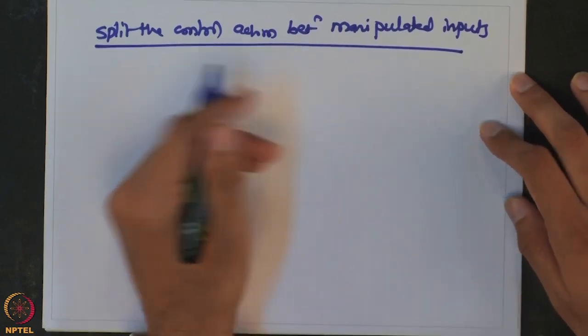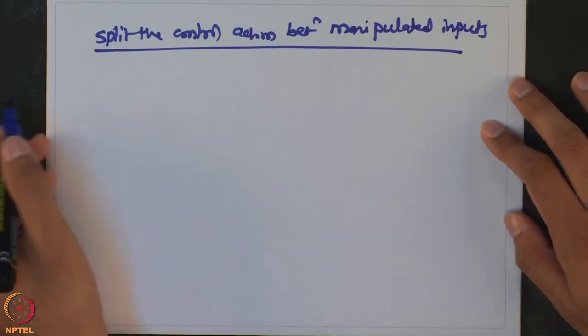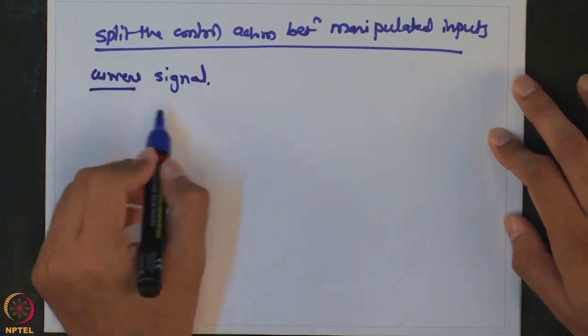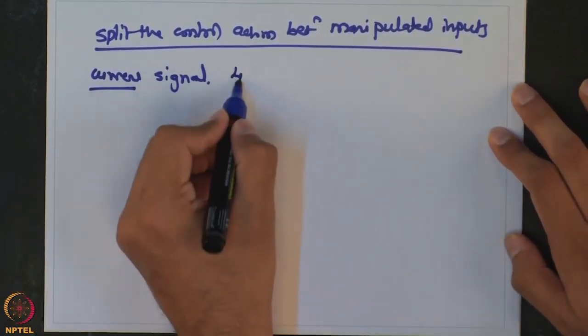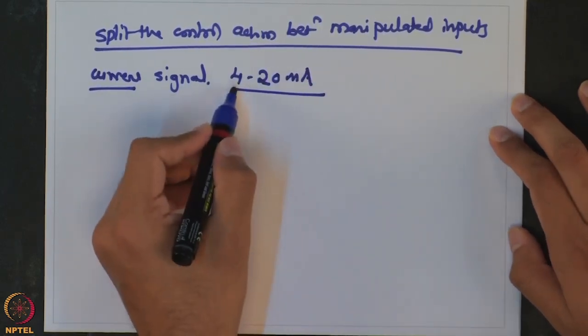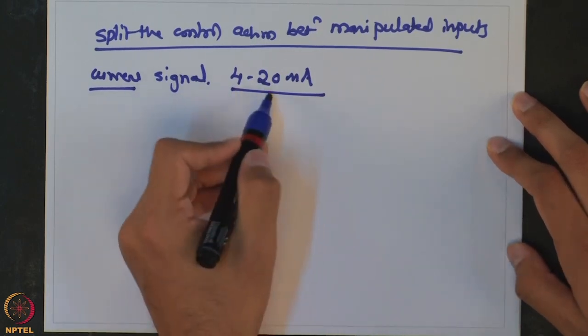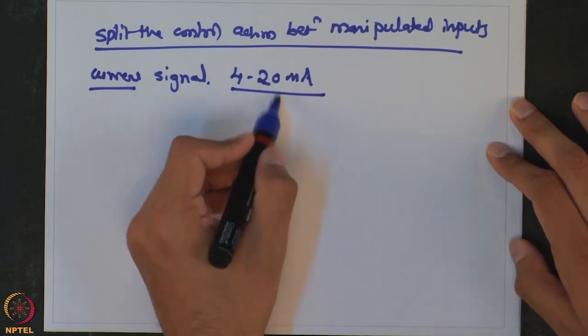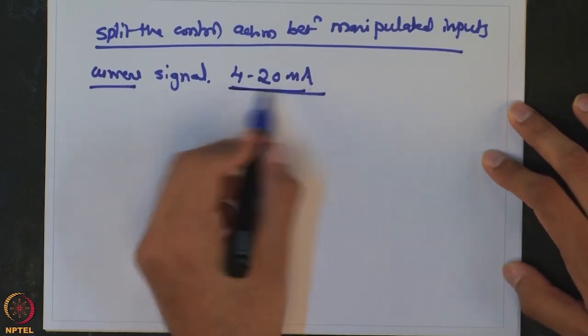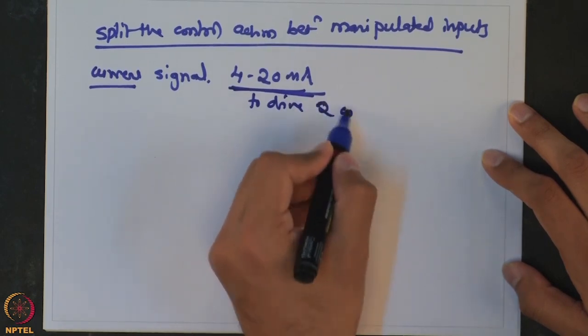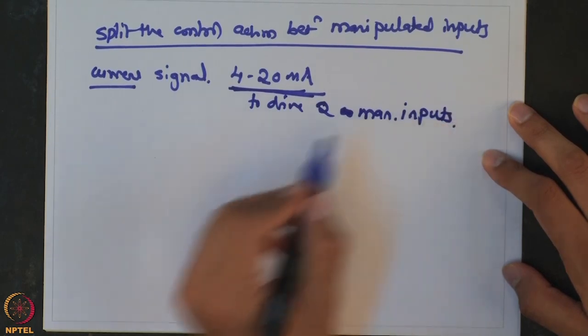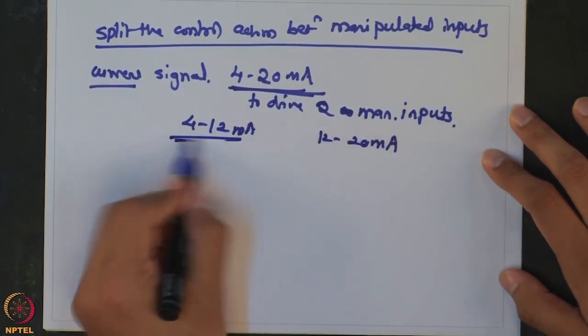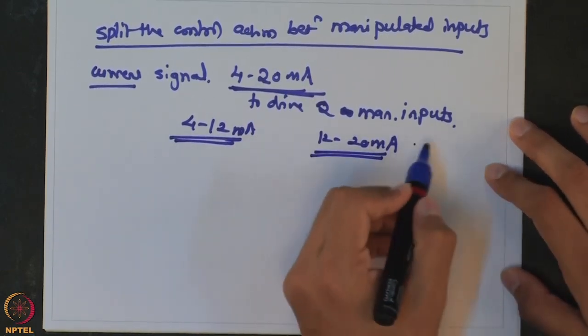How do we split this automatically? Recall that the controller sends a current signal to the manipulated input. Nowadays the standard is a current signal between 4 to 20 milliamperes, where 4 mA means the valve should be at its zero state and 20 mA means the valve should be at the other extreme. For a fail-close valve, at 4 mA it is completely closed and at 20 mA it is completely open. We use the same range to drive two manipulated inputs by splitting it — for example, 4 to 12 mA for one valve and 12 to 20 mA for the other. That is why it is known as a split range design.